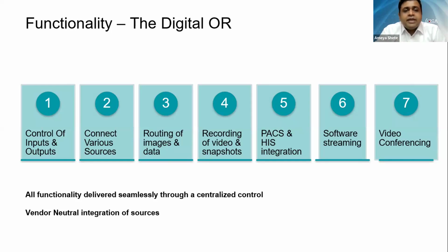So this has to be controlled through a central monitor or a central system. And a very important part is that it has to be vendor neutral. You should be able to connect sources from any vendor, or you should be able to connect a camera, a laparoscope, an anesthesia machine from different vendors and bring them onto a single platform.